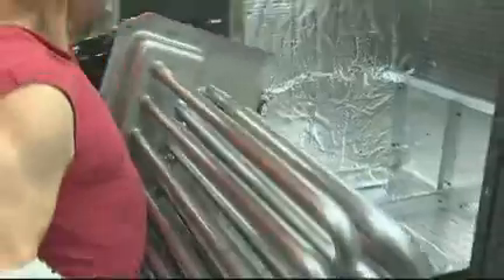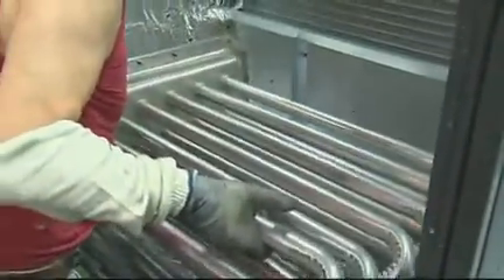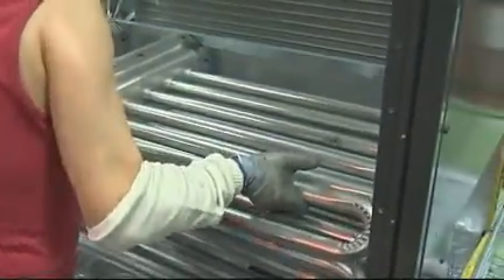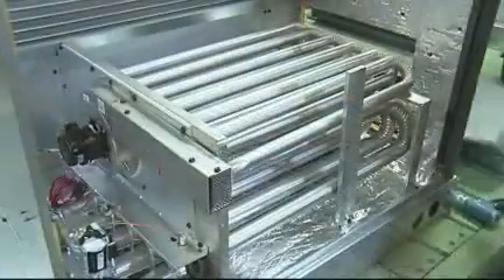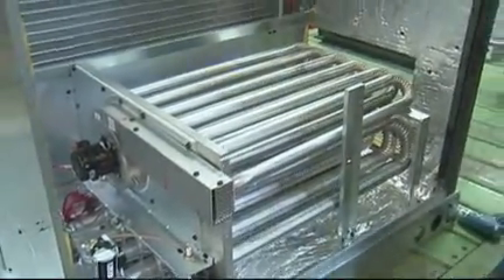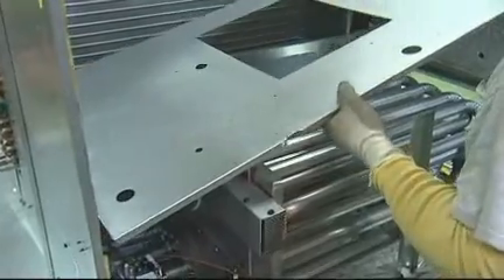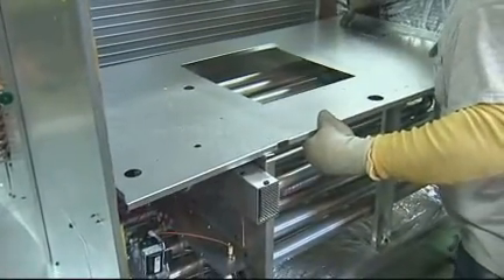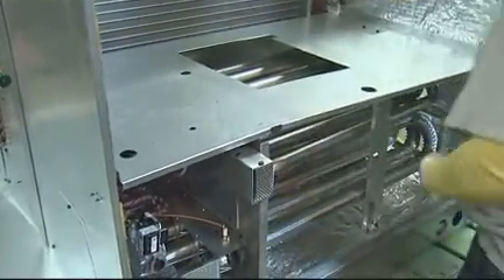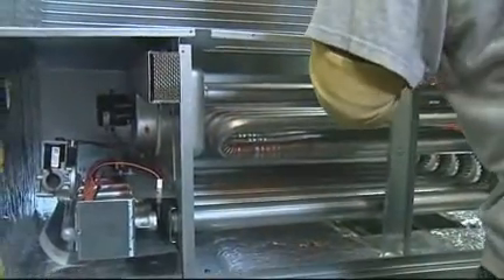Here you see in the unit the complete heat exchanger. And I might point out that we use the same tubular design with a wrinkle bend. Right, the wrinkle bend technology. That we use in our residential. We've got a heat exchanger that's gone over 2 million cycles without a failure. That's the best quality heat exchanger in the industry. I bet. And there you see it installed in a unit.